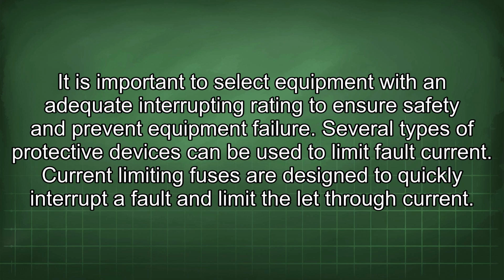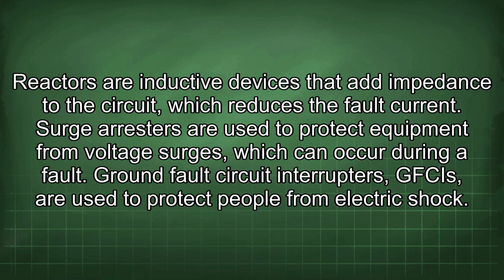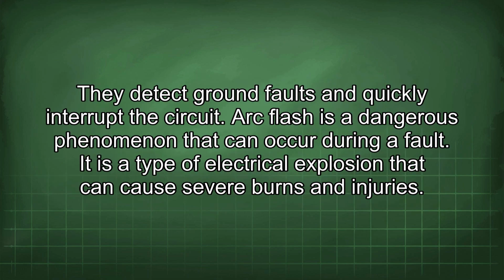Several types of protective devices can be used to limit fault current. Current-limiting fuses are designed to quickly interrupt a fault and limit the let-through current. Reactors are inductive devices that add impedance to the circuit, which reduces the fault current. Surge arresters are used to protect equipment from voltage surges, which can occur during a fault. Ground fault circuit interrupters, GFCIs, are used to protect people from electric shock. They detect ground faults and quickly interrupt the circuit.